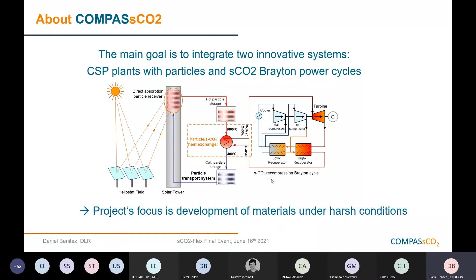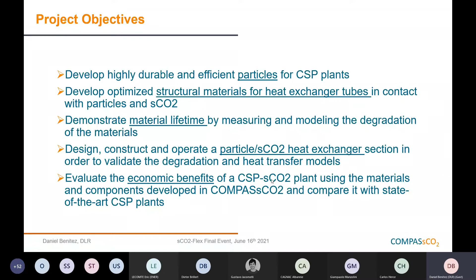So as for the objectives, we will work on the development of, let's say, new particles for CSP plants. Then also work on the structural heat exchanger tubes, which are in contact with the particles and the supercritical CO2. To demonstrate the lifetime of the materials by testing them and modeling the degradation. Then to design, construct, and operate a section of a particle, CO2 heat exchanger, which we'll use to validate the models. And finally, to evaluate the economic benefits of such a plant, and of course, compare it with the state-of-the-art CSP plants.